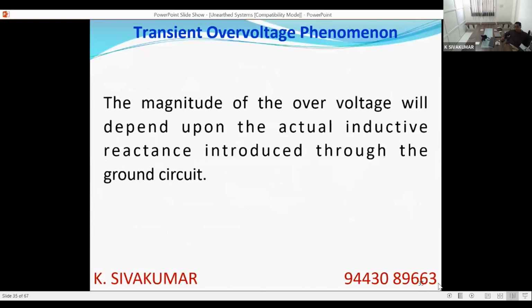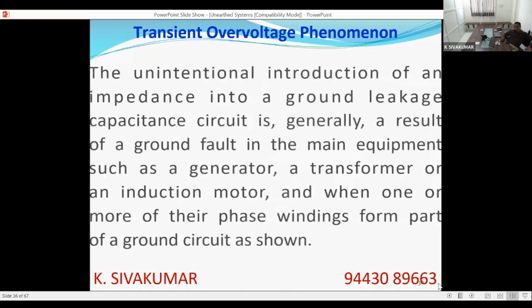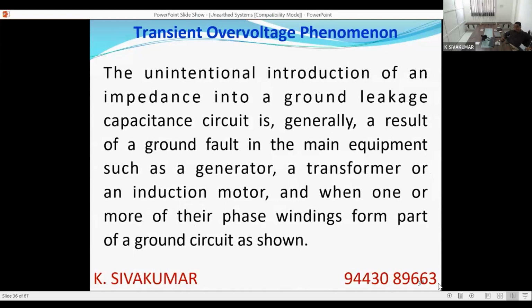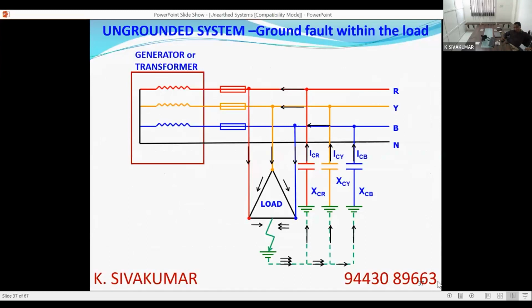The magnitude of overvoltage, for which precise calculations are available which we will see, will depend upon the actual inductive reactance introduced in the circuit. What is the source of the inductive reactance? The unintentional introduction of an impedance in the ground leakage capacitance circuit is a result of a ground fault in the main equipment such as a generator, transformer or induction motor, when any of these windings get earthed like this.